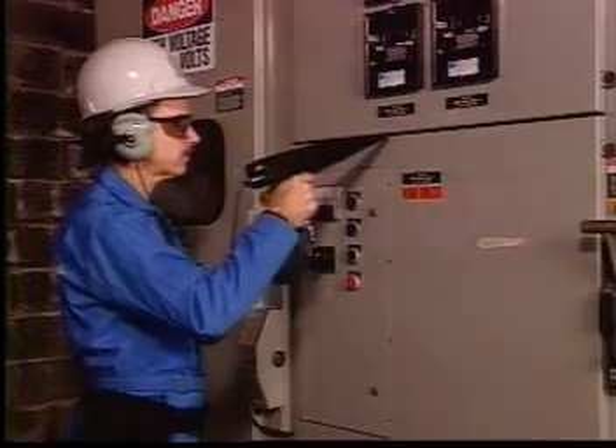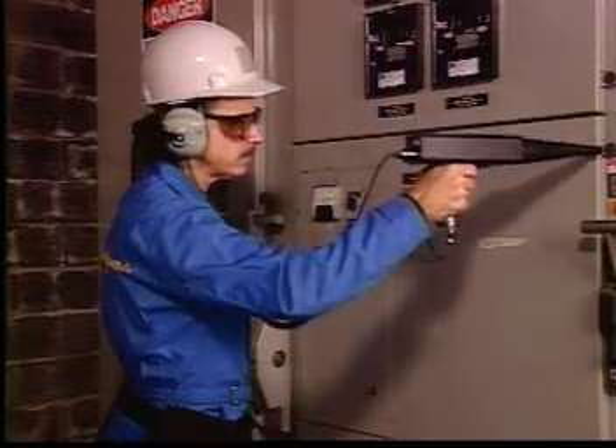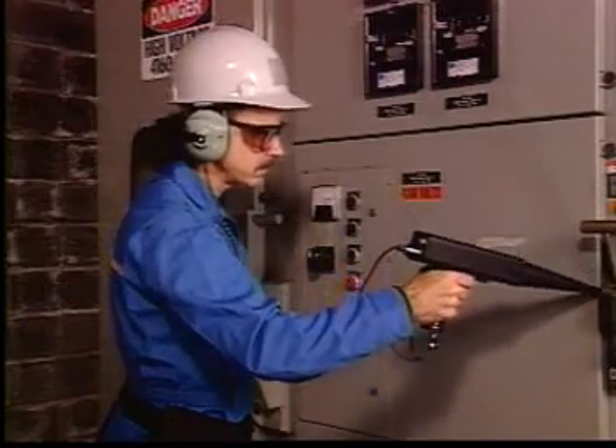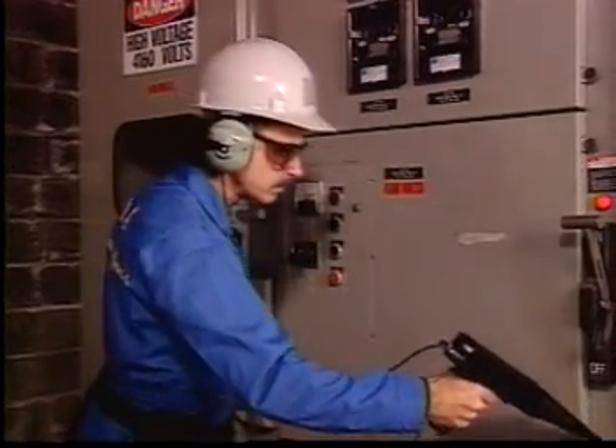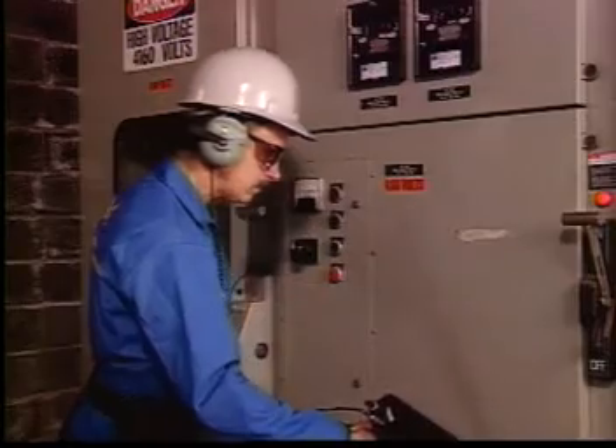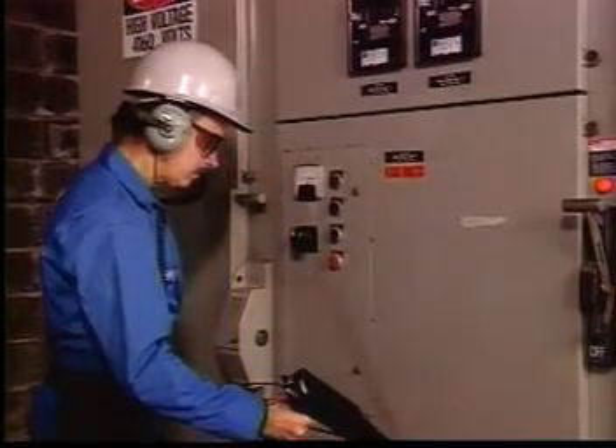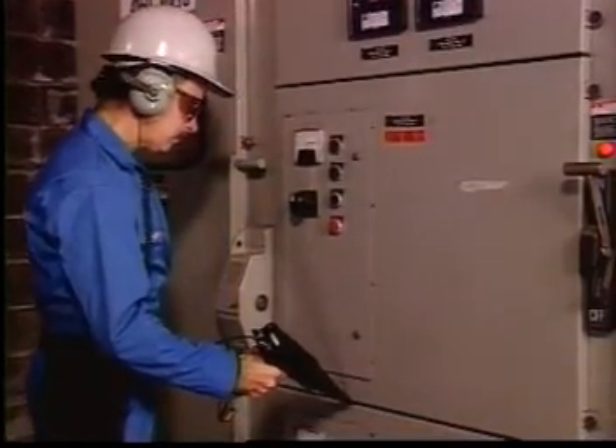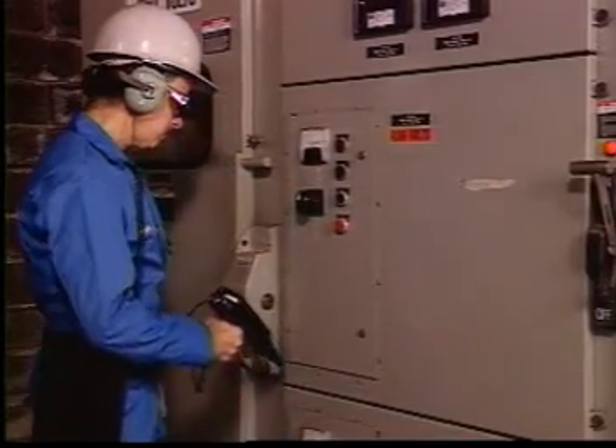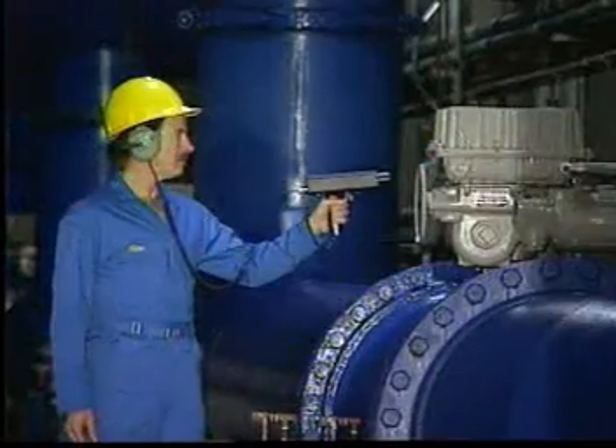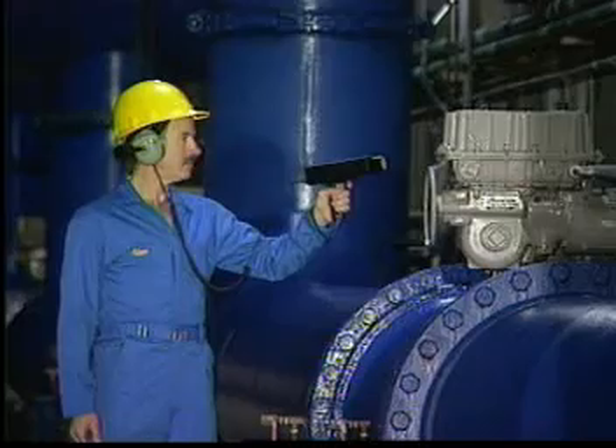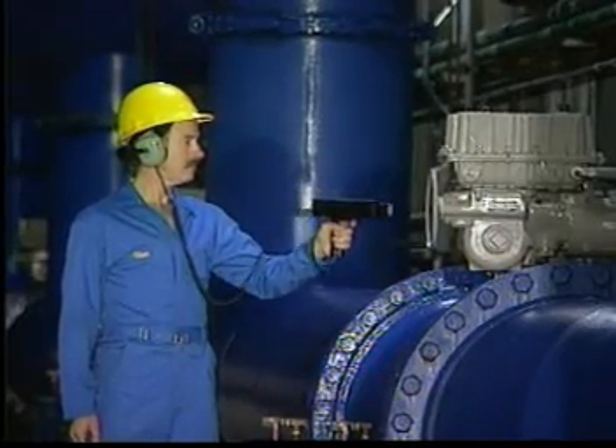Arcing, tracking, and corona may be present without creating hotspots that can be detected by infrared testing. When these conditions exist, there is potential for failure. Immediate action can avert disaster. The ultraprobe expands your field of view and readily identifies these dangerous conditions. There are new applications and techniques devised for the ultraprobe all the time.